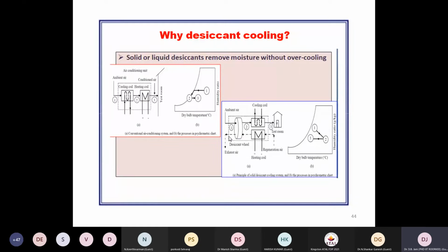operations can occur simultaneously with this integration, and the total process is shown on the psychrometric chart by its dehumidification and sensible cooling process by respective state points, so two process air flow rates are required. One is the process air flow for cooling, and the other is the reactivation air, reversibly, to maintain the drying operation. Otherwise, what happens? The desiccant will become saturated, and its operation effectiveness drastically drops, reducing the dehumidification rate.